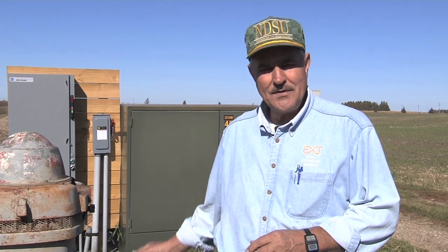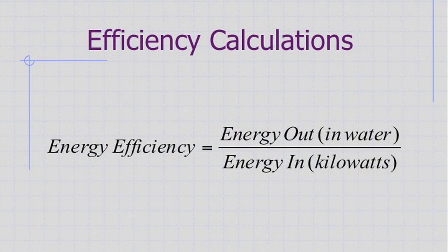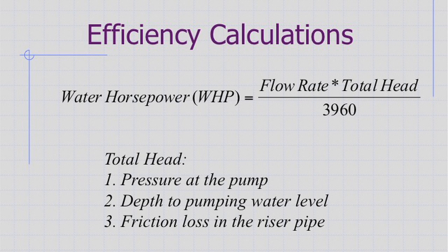So hopefully, from information about when the well was drilled, you get an idea of what the pumping water level is. And once you have that, you can calculate how much actual power is in the water. In order to do the pumping plant efficiency calculations, we need to measure the energy out, which is in the water, and the energy in, which is through the electric meter. To measure the water horsepower, we need to know the flow rate and the total head. And this simple formula shows how to calculate that.